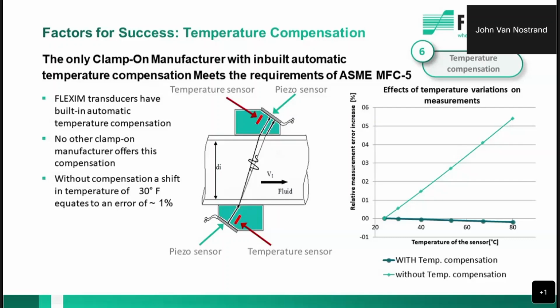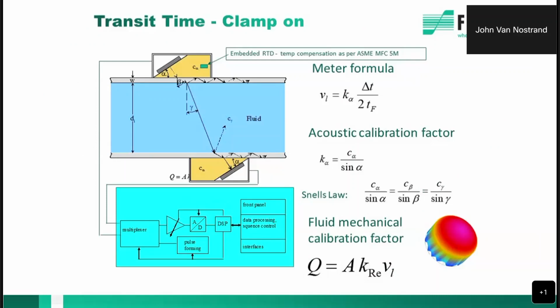And by the way, that temperature compensation is called out in ASME MFC 5M as a standard. FLEXIM meets that standard where other clamp-on meters don't offer it whatsoever. They don't even talk about it. So it's really important. So when it comes to Snell's law, temperature becomes very important. What we're really looking at is the beam angle, which is the Y dimension here. And that beam angle changes with temperature.